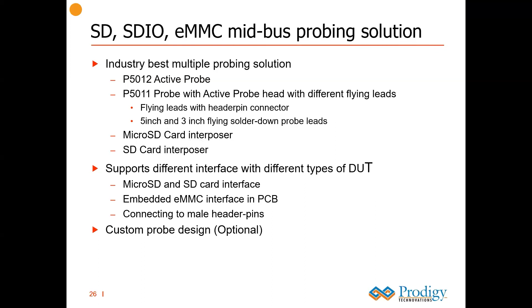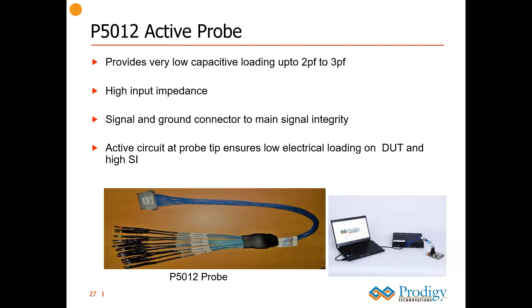Now looking at the P5012 active probe, this is a probe cable with the flying lead set. You have an active circuit right at the probe tip. This probe tip has an isolation circuit at the front end so that the high-speed 200 megahertz signal which gets into this probe should not reflect back to the device under test. So we have made sure that the probe tips are isolated from the device under test, and we are just tapping a portion of the signal and taking it to the protocol analyzer. This will ensure the signal integrity in the device under test, as well as let us do protocol analysis without any challenges.